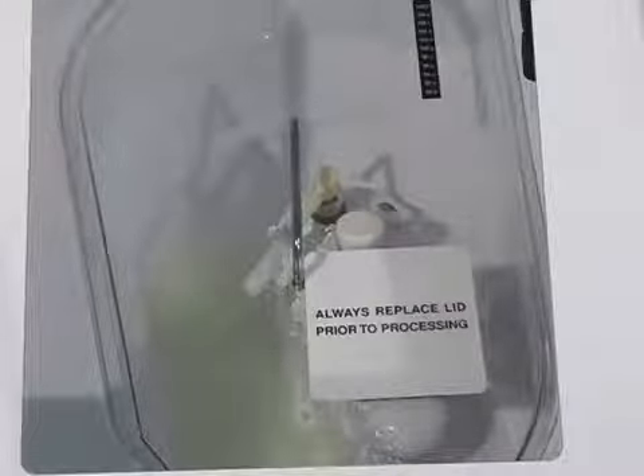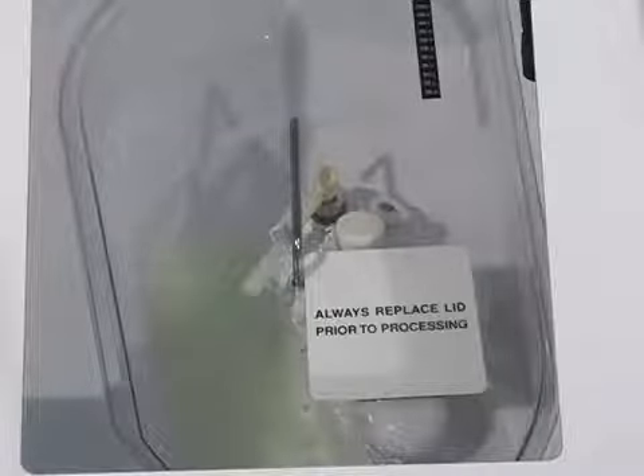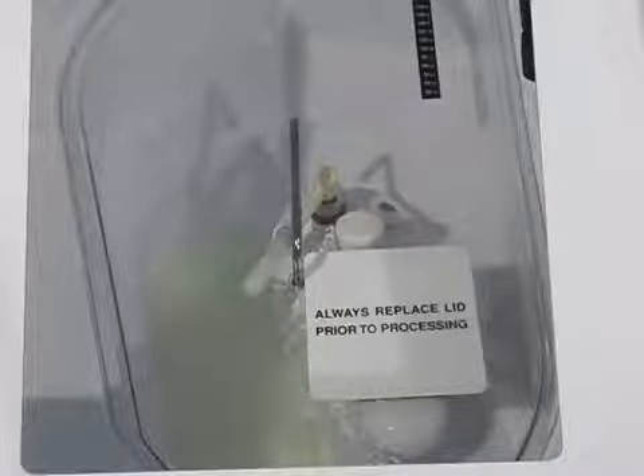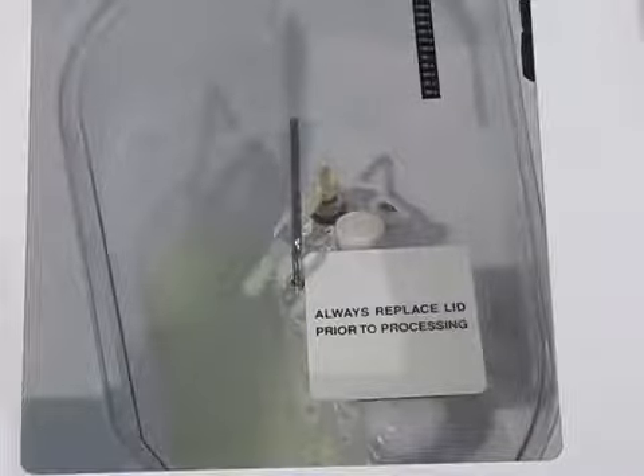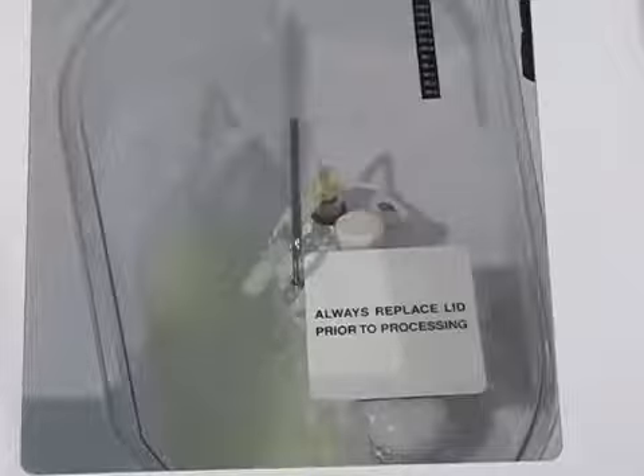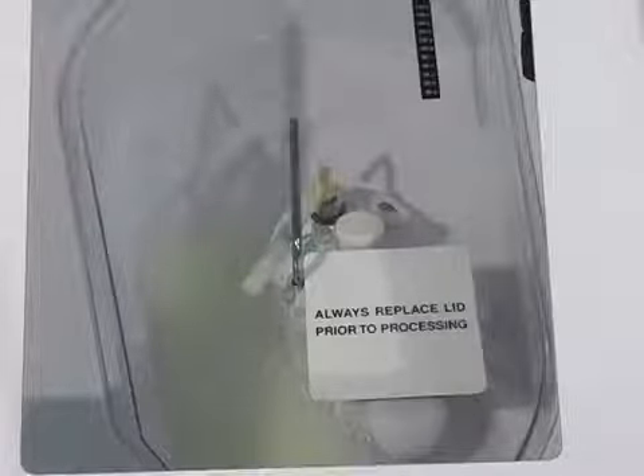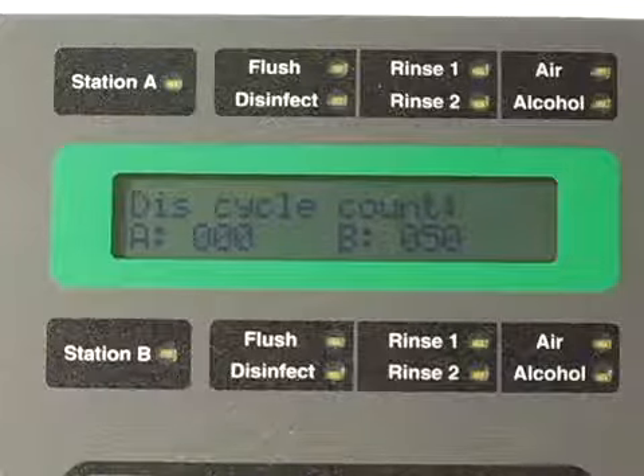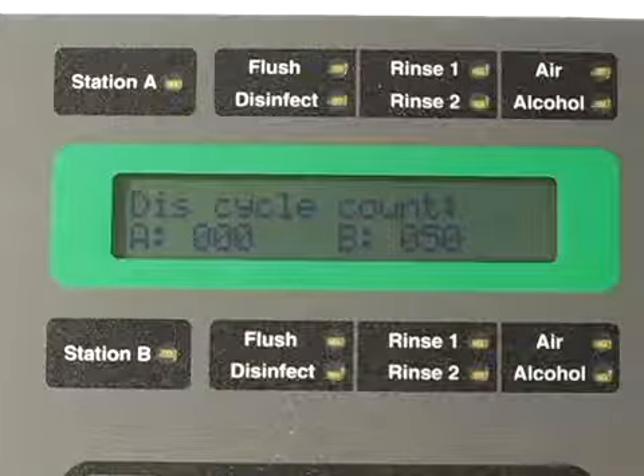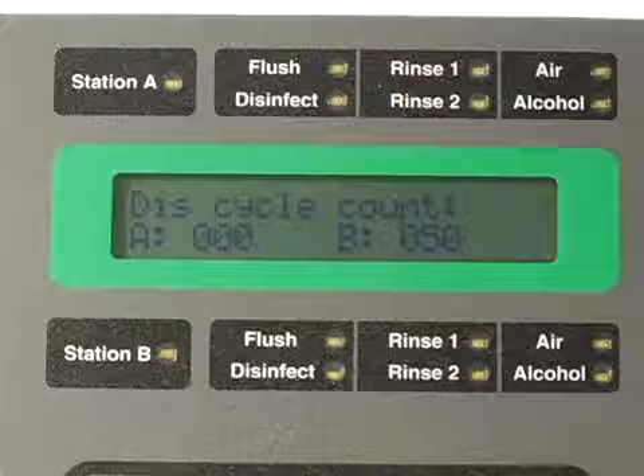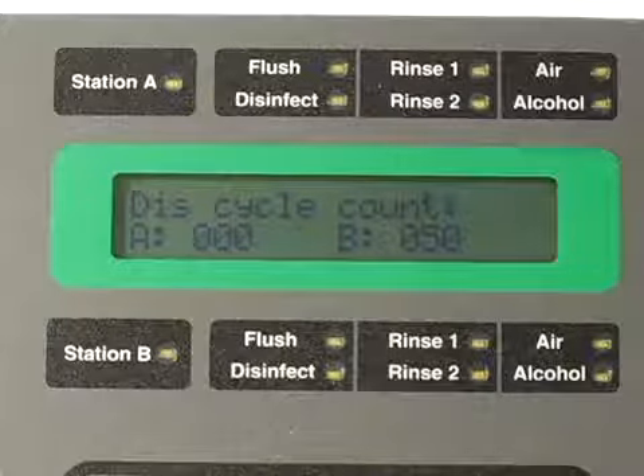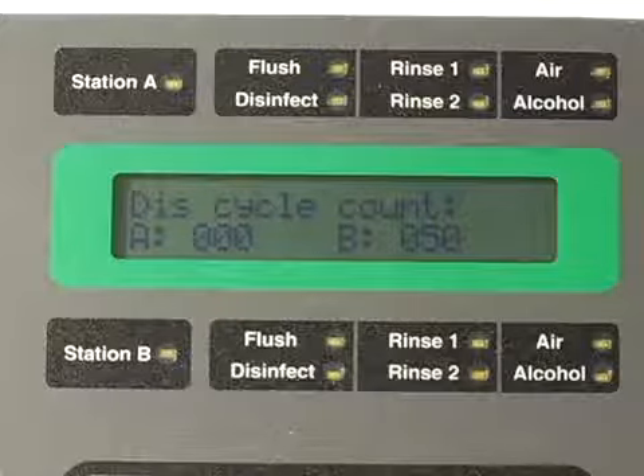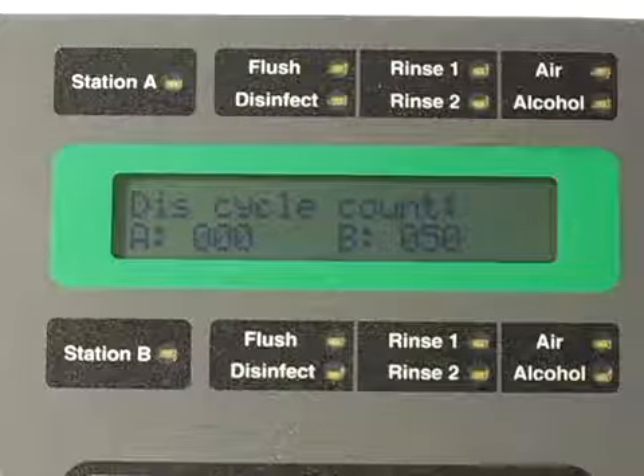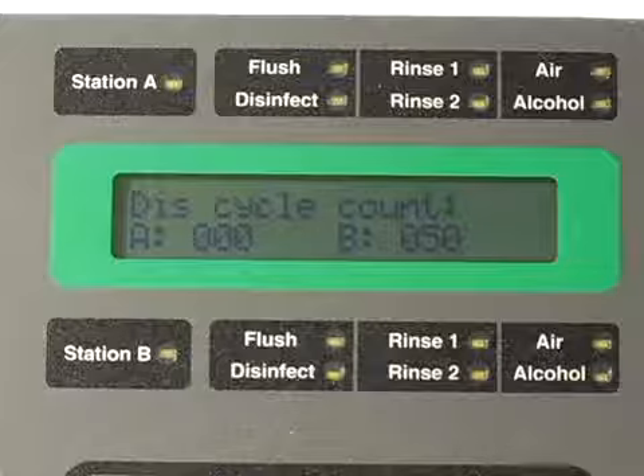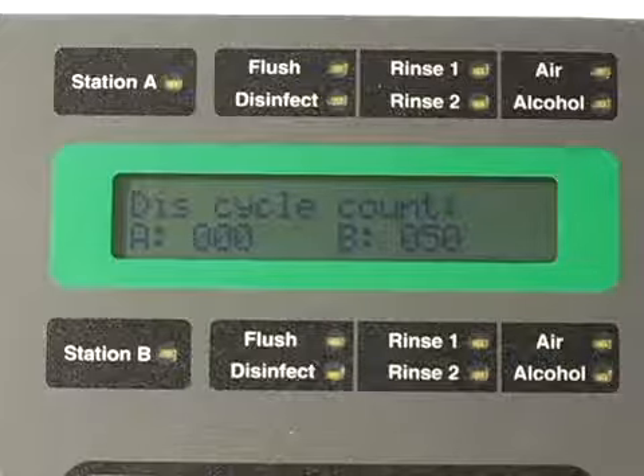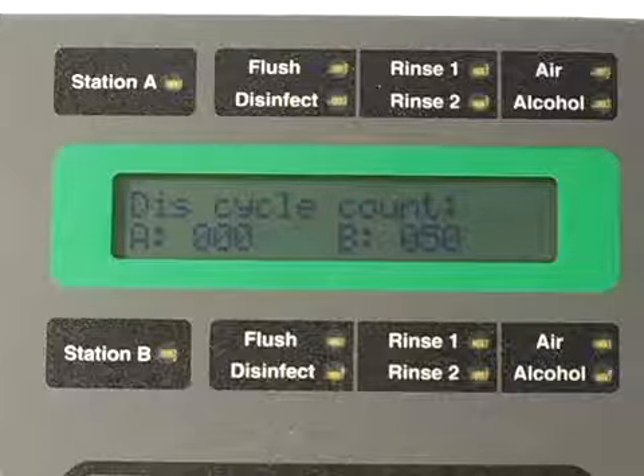After this, water is sent into the basin and down the drain to rinse it of any disinfectant residue. It is also possible to dump disinfectant through the onboard transfer pump. Details are in the DSD-201 instruction manual. When the disinfectant has been discarded using the disinfectant dump function key, the DSD-201 disinfectant cycle counter is automatically reset to 0. If the disinfectant has been removed from the reservoir using the onboard transfer pump or Medinute, the user should reset the cycle counter manually by using the setup function keys. We'll learn more about this in Section 8.